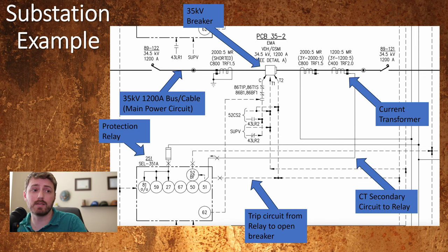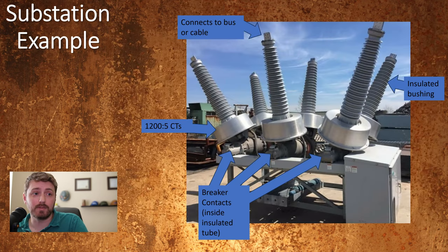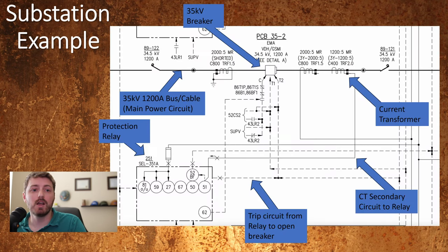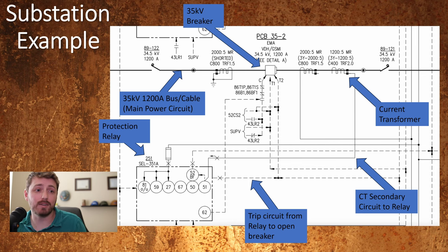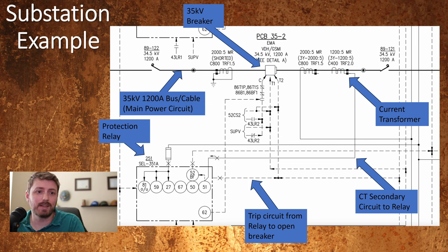Moving back to relays — if we look at this example of a transmission substation, the primary side of the CT, the bus, is at 34.5 kV — that's 35,000 volts — and can carry up to 1,200 amps. It's a lot more power than a thermal breaker can reasonably handle. But on the secondary side of the CT there's much less energy according to the ratio listed here — 1,200 amps on the primary would be about five amps on the secondary. This also provides galvanic isolation from the bus, so we can treat the secondary wiring as safe low-voltage wiring. Low voltage and five-ish amps is a lot easier to deal with and plug into a precision instrument than 35 kV and 1,200 amps.